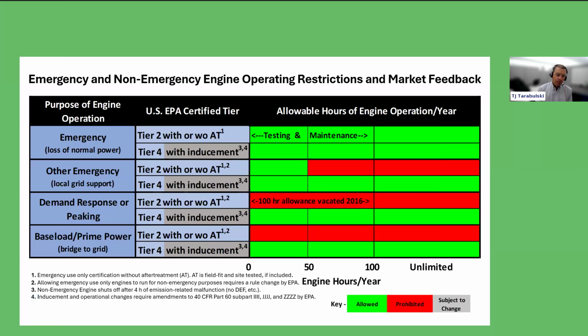The fourth row is the baseload prime power or bridge to grid, as Alan was describing. This describes the Tier 4 certified product may be used for this purpose, and potential changes to EPA regulations could allow Tier 2 engines with advanced controls to run additional hours. They'd be meeting the same emissions levels as the Tier 4 product in that case, but it relaxes the restriction of limiting their operation to emergency hours only by adding the after treatment. As noted earlier, for all these scenarios, additional state restrictions can apply.